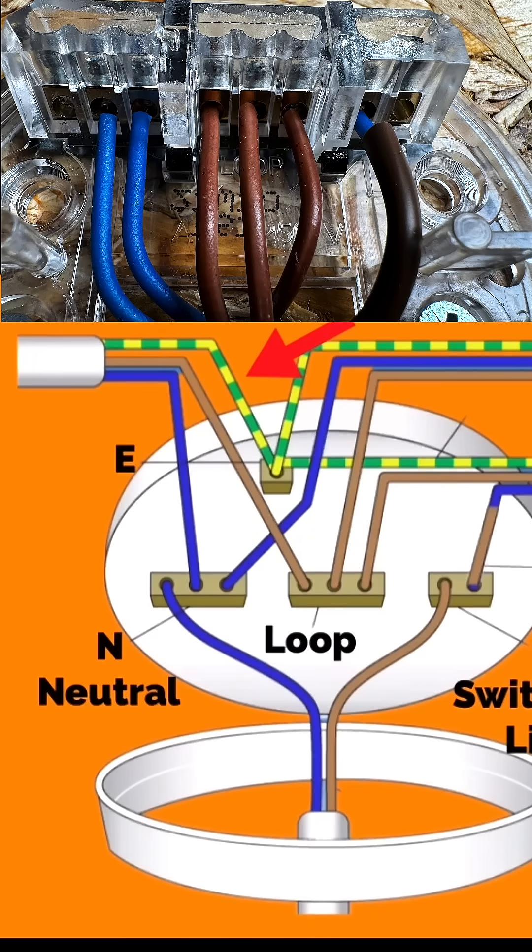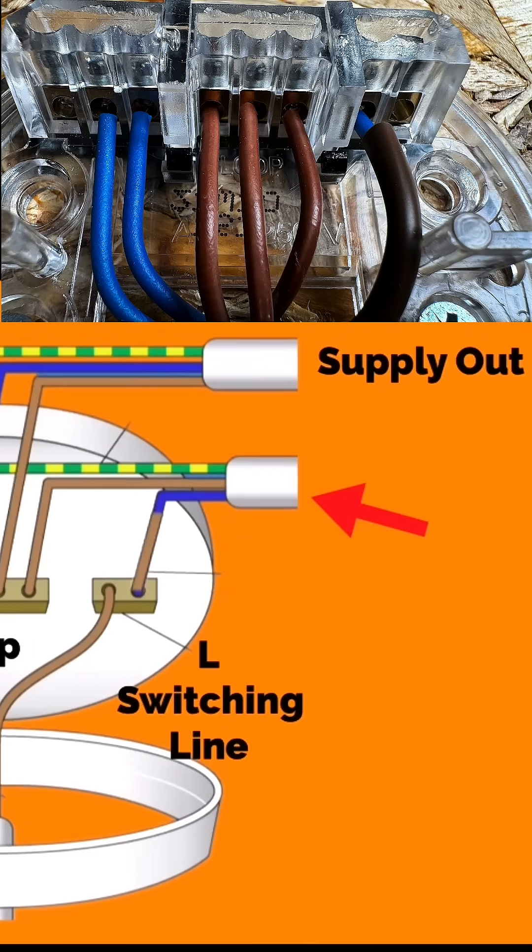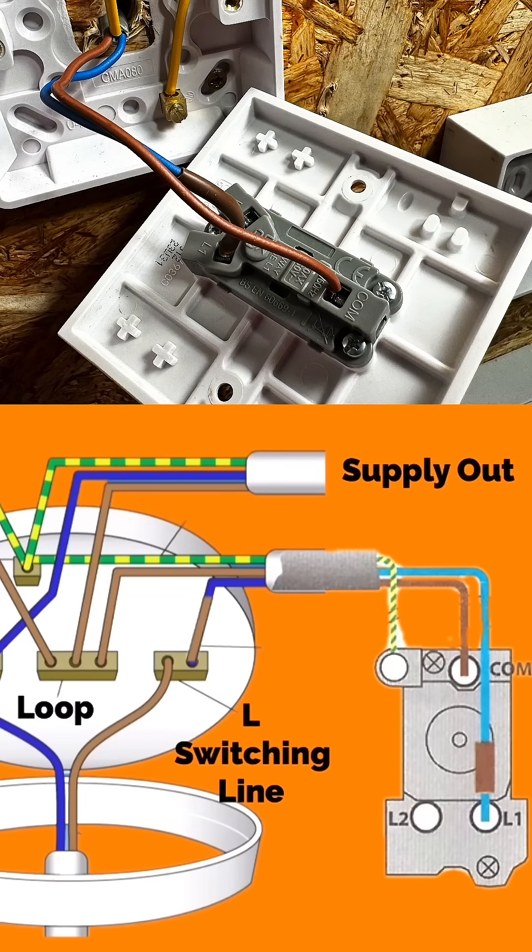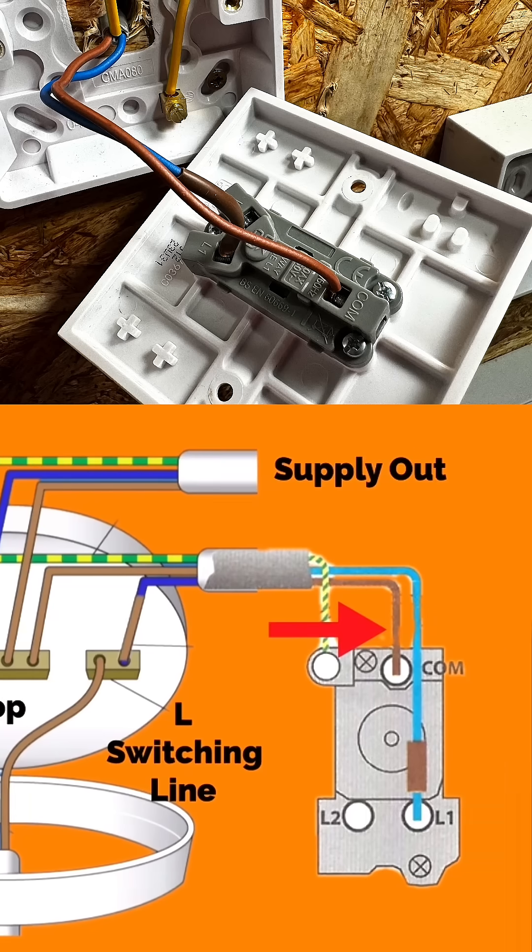The bottom right-hand cable is a switch drop. If we see that the switch is, say, a one-way switch, we take a permanent line from the looping terminal in the centre and it goes down to the one-way switch connected into the common terminal. We have a switching line conductor returning.